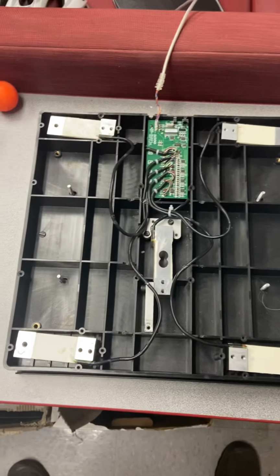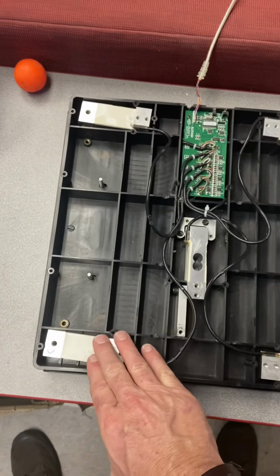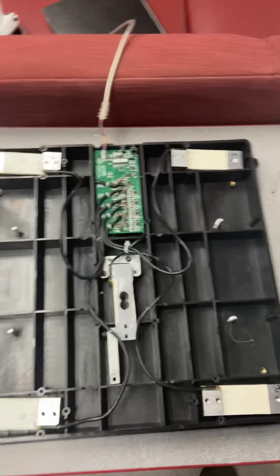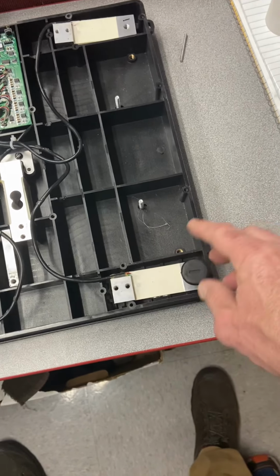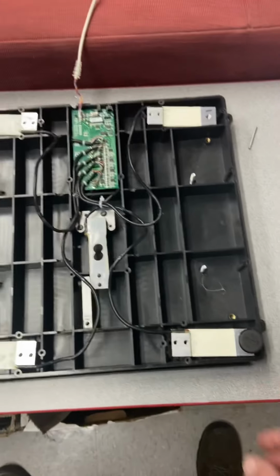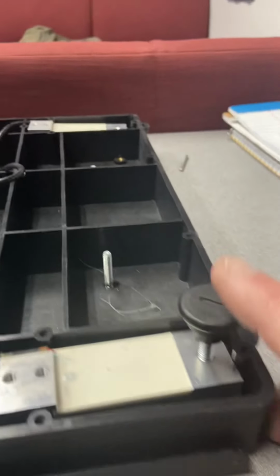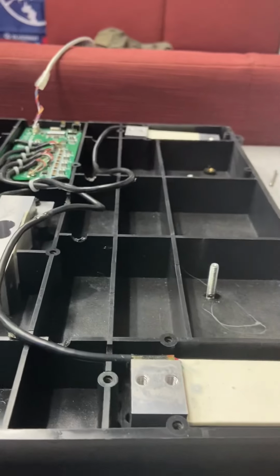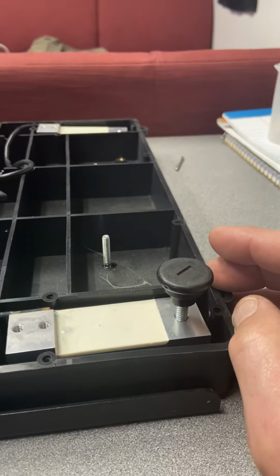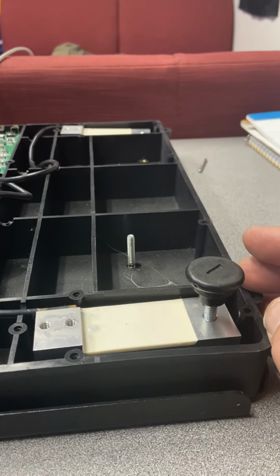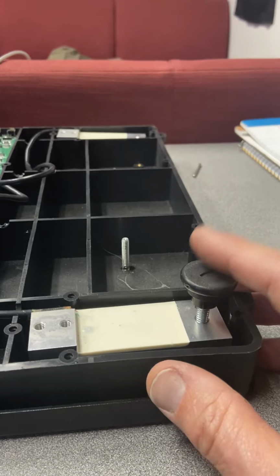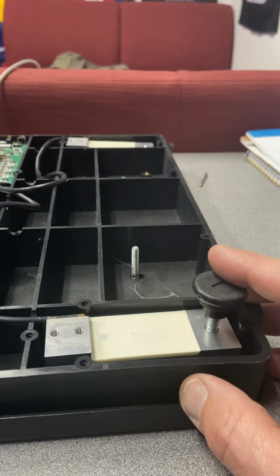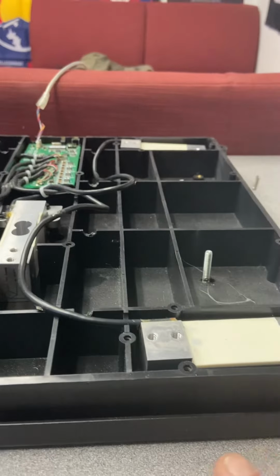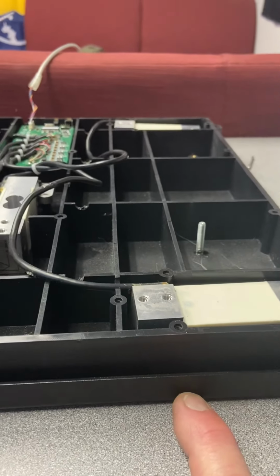One important thing: if you ever use this force platform, make sure the feet are plugged in correctly. If a force platform is missing a foot, a peg, it's no good. These pegs are important, and they need to be screwed in correctly so that every one is in contact with the ground when set up. Ideally, if I flip this back over, the platform should be level.